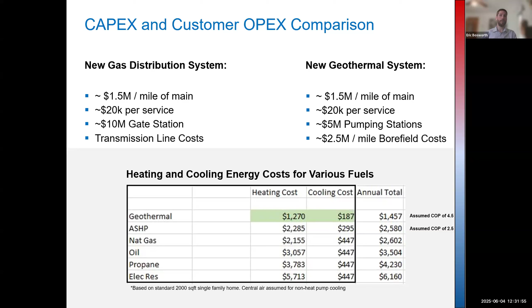So what does that look like practically? On a system like the one in Framingham, maybe you throw a dry cooler or a large air source heat pump onto the system, wait until energy cost is lowest, then kick it on to pre-cool the system, bringing the temperature down in the water and underground. Then you turn it off and ride through the peak. That lets you arbitrage the time of day because you're connected to a thermal storage system. So it's worth exploring whether you can leverage that opportunity in your utility market.